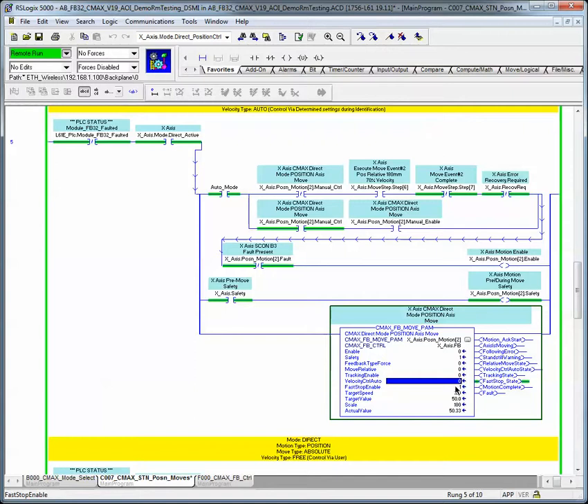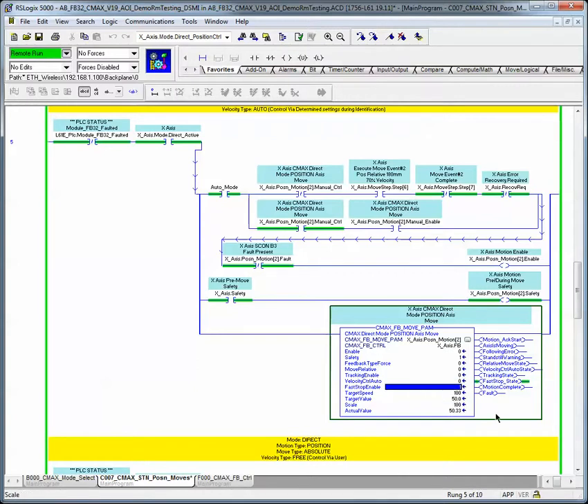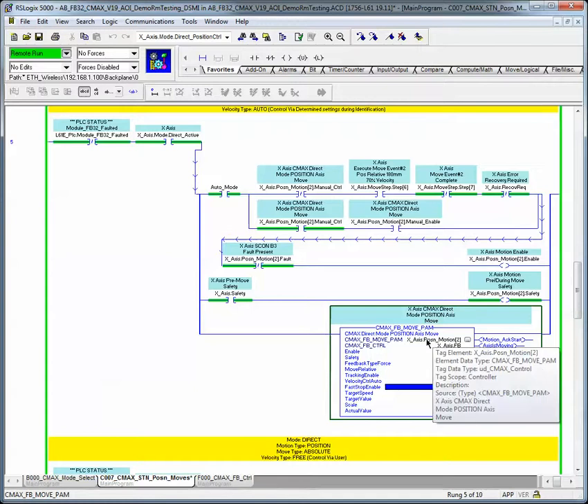Fast stop. Velocity control auto is at the user's discretion as far as whether they use the user-defined parameters for accel or decel velocity, or the identified maximum values during the identification process — referencing that in the literature. The fast stop enable is another feature that either means you're going to do an accurate stop or as quick a stop as possible, and then give you your motion complete.